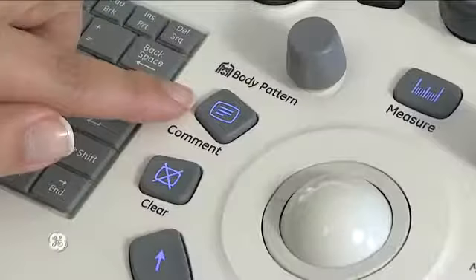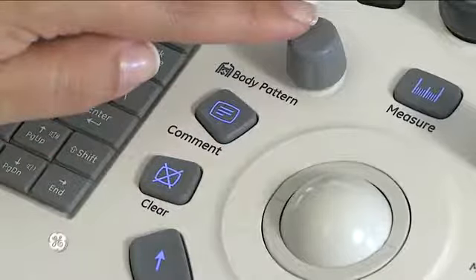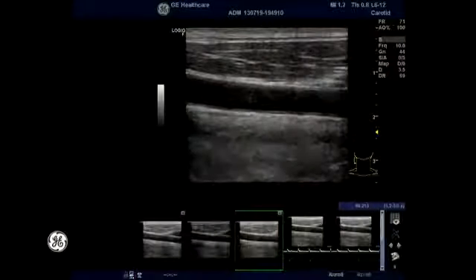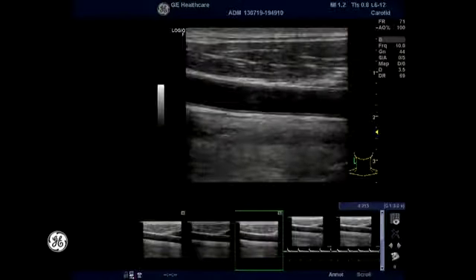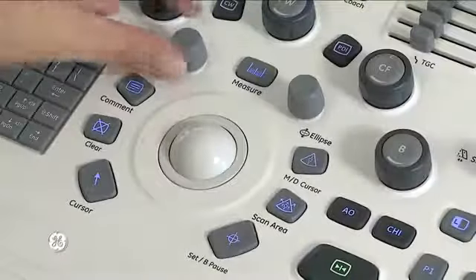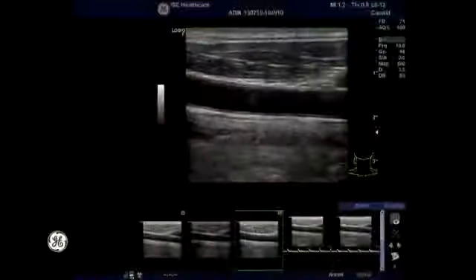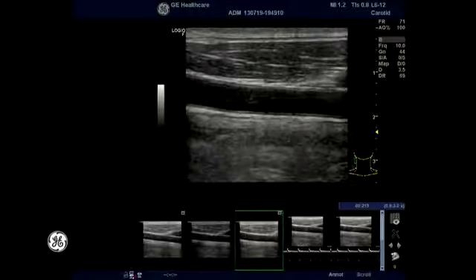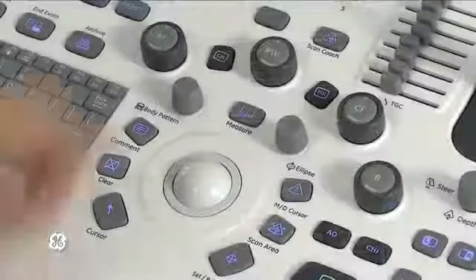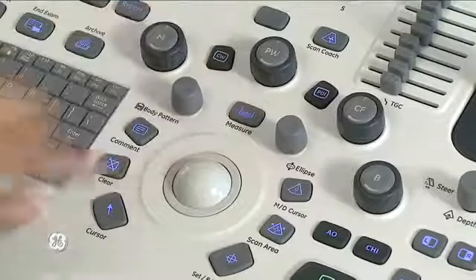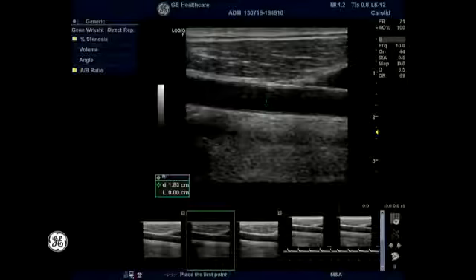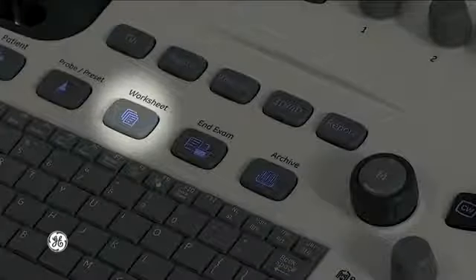The body pattern function will be activated by pressing the body pattern knob. The body pattern will automatically be selected based on the active application used for imaging on the touch panel. The probe marker is also displayed as a green indicator on this body pattern. Rotate the body pattern knob to adjust the direction of the probe marker. The measurement function is enabled after moving the cursor to the measurement zone and selecting the parameters required to be measured. The measurement results can be displayed through the key Worksheet within the workflow zone.